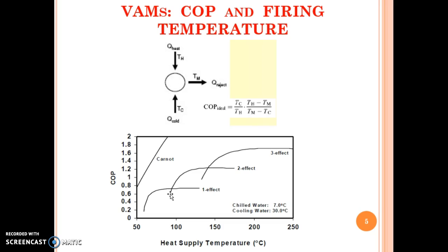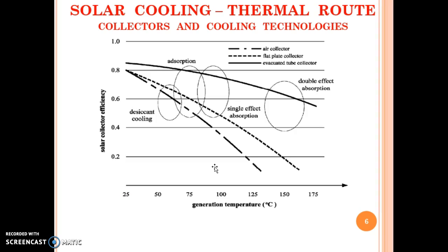And if energy is available at higher temperature, then it's advisable that you go for double effect machines, and if temperature is even higher, one can go for triple effect machines. And as the number of effects are more, the efficiency will be more, but you will be using different type of collector—that is, a better quality of collector if you want a higher temperature.